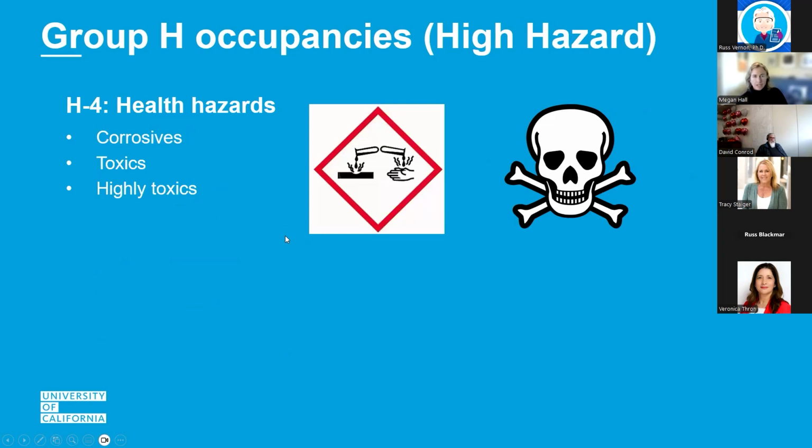H4 is for health hazards: corrosives, toxics, and highly toxics. These are things that are acutely toxic or corrosive that cause irreversible tissue damage. Things that are corrosive to metals are not regulated by the fire code, but you could still store them in here if you wanted to.